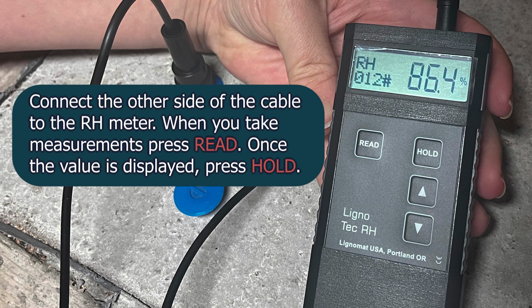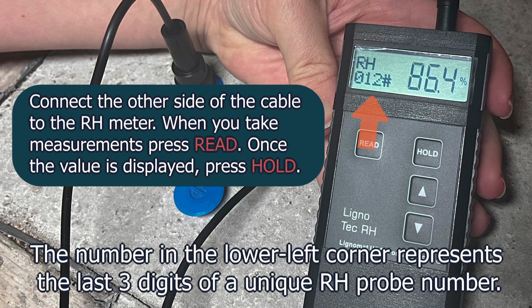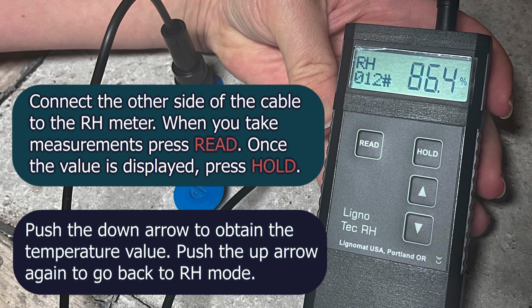When you take measurements, press the read key. Once the value is displayed, press the hold key. The number in the lower left corner of the display represents the last 3 digits of a unique RH probe number. Push the down arrow to obtain the temperature value. Push the up arrow again to go back to RH mode.